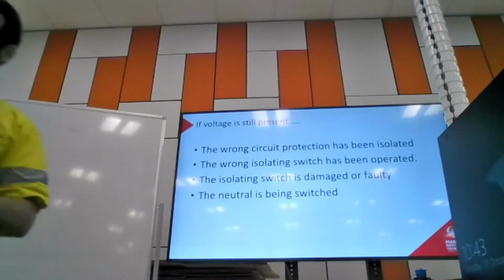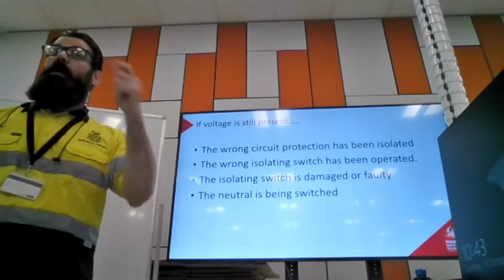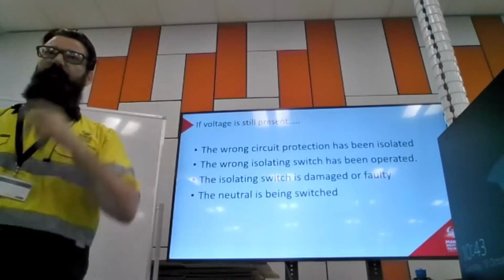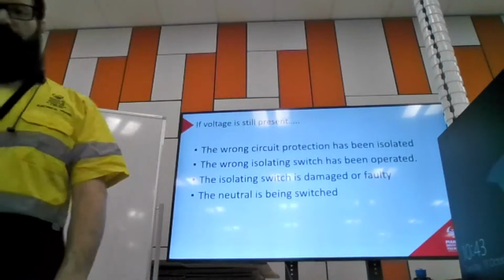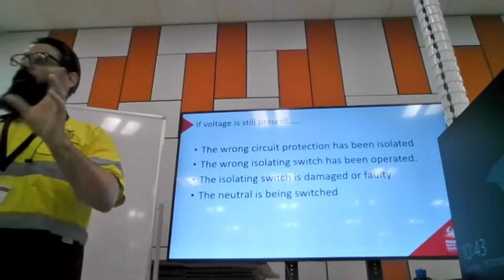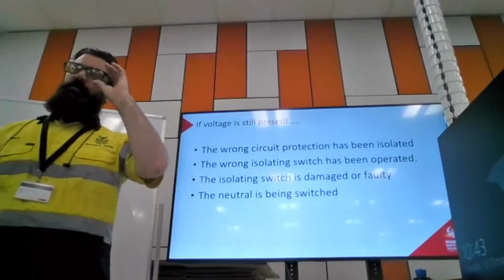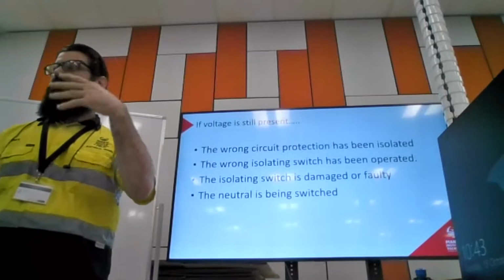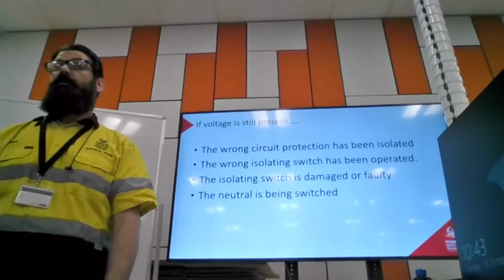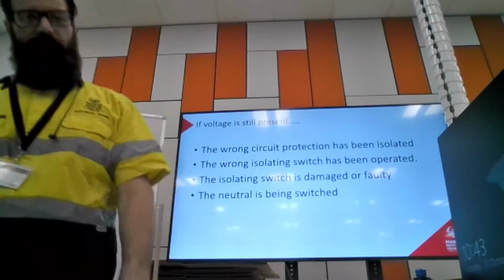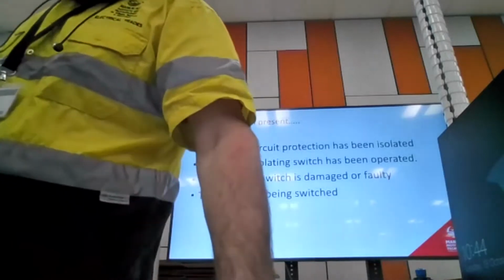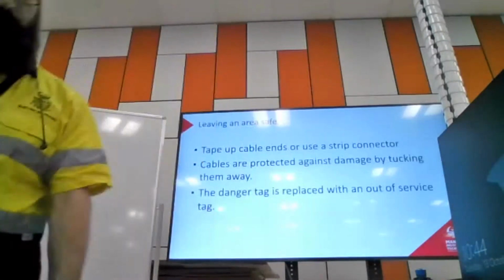I was only involved in that one because I was asked to be part of the investigating team to figure out what went wrong. That's actually one of the reasons why we don't generally use double pole switches and don't switch neutrals. But in a fuel station situation, we do use double pole switches. So if the neutral is being switched, that can cause us all sorts of issues.